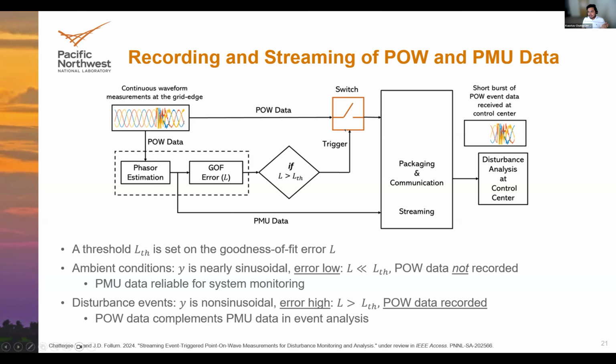That complement is coming from point on wave data. So you have a condition-based switching, a condition-based reporting here. If your error goes higher than the threshold, you close the switch and your point on wave data is also recorded and reported to the control center. How we do that streaming, I'll come to that later, but that's what gets reported at the control center. So you have continuous streams of PMU data and then short bursts of point on wave data, which are then analyzed for disturbance signatures.